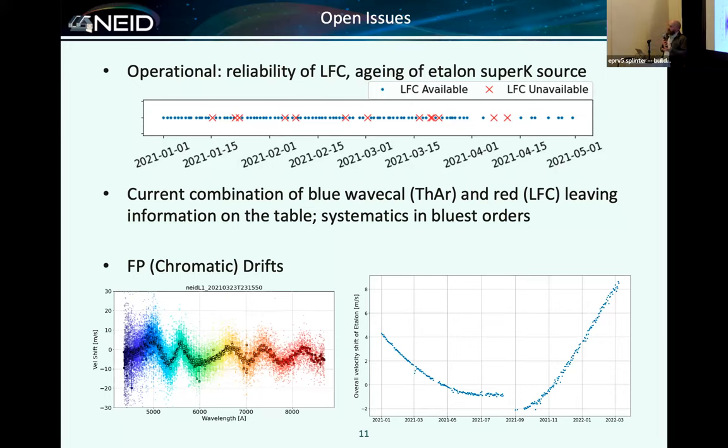But it's also difficult to predict in advance whether it will work or not work for any given night. So this presents an operational problem. We take exposures assuming that it's working, which means that sometimes we end up with blank exposures in our cal sequence that the pipeline has to handle. We end up with irregularly exposed exposures that have changing flux values through them, and this has complicated things quite a bit. We're not doing a good job right now of cleaning that up and handling it robustly, but it's on the list, if I can stop restarting the instrument every 9 months.